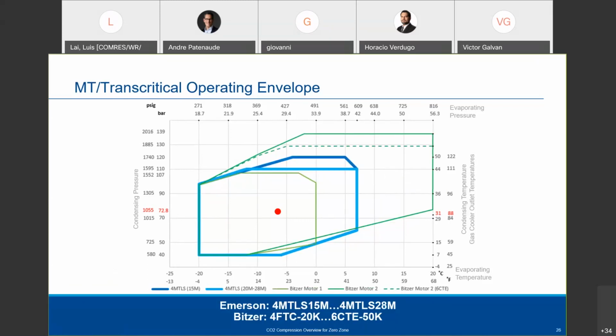So that's super important. Now, why is this envelope a little bit different? Well, as you get into larger displacement compressors, even the Emerson envelope changes a bit. So the 150,000 BTU model, the 4MTLS15M is the dark blue, goes up to 120 bar or 1,740 pounds. But the 3 largest displacements, they're down here at around 110 bar. Again, compared to Bitzer's number 1 motor, we're higher in head pressure, we're higher in saturated suction.